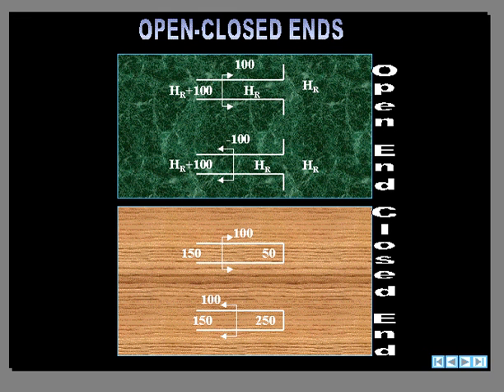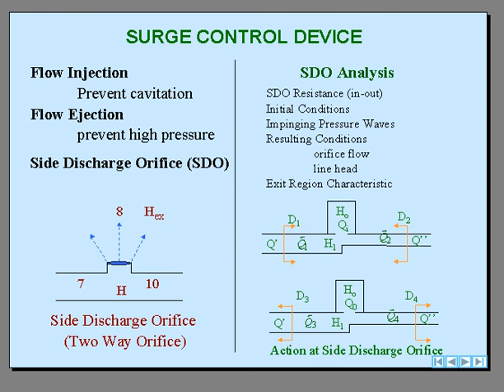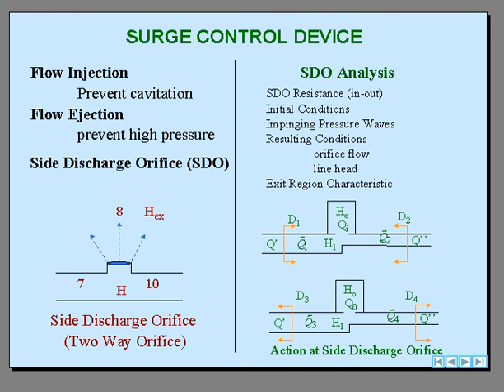We have surge control devices. These are almost always based on flow entering or leaving the system. And we set up a subroutine to handle these devices. These include open and closed surge tanks, feed tanks, bladder tanks, pressure relief valves, surge anticipation valves, and air valves, which have an effective inflow and outflow orifice.